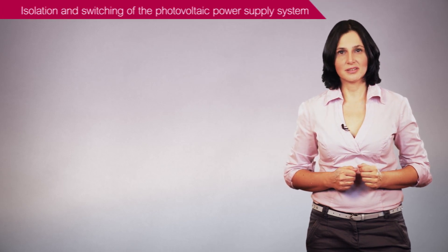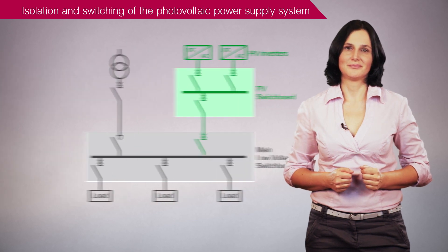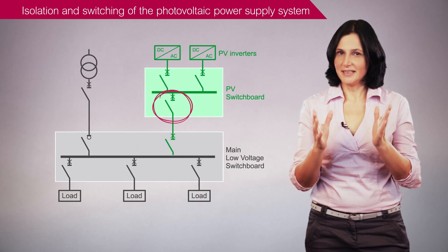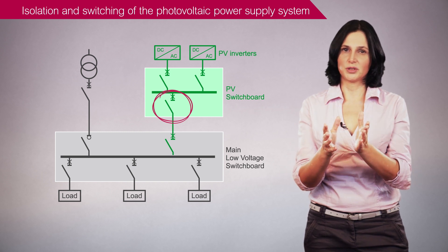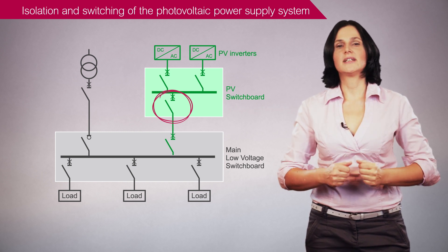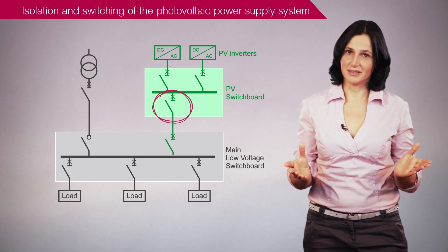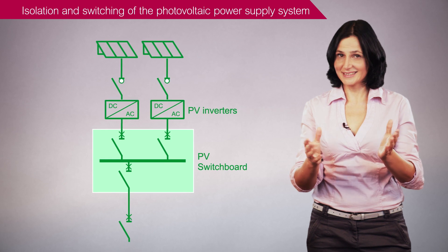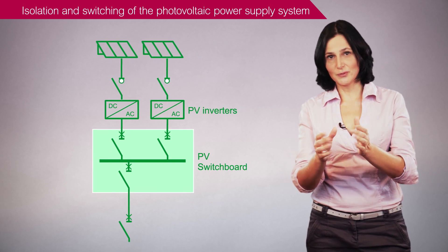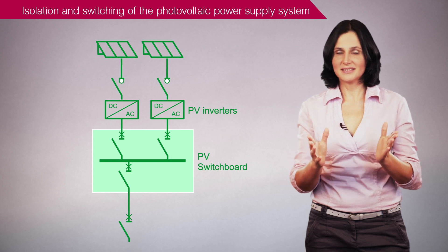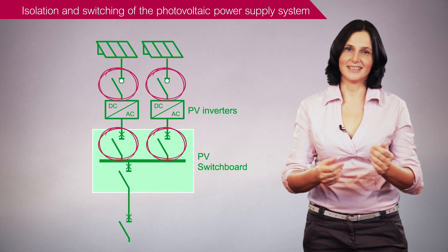Let's consider the isolation and switching of the photovoltaic power supply system. An AC disconnection device must be located at the photovoltaic switchboard to isolate the photovoltaic system from the rest of the electrical installation during maintenance. Additionally, an isolation function must be provided for the photovoltaic inverters by disconnection means on both the DC side and the AC side.